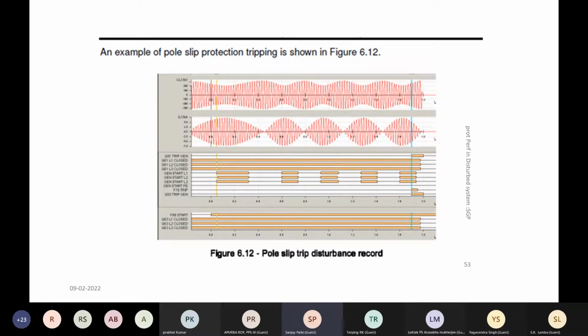Likewise, there is a number of pole slips which a generator can tolerate. Every pole slip results in stress on the generator in terms of mechanical forces. So there is a risk of damaging mechanical components due to torsional stresses, as well as a risk of loosening of the winding within the slot due to vibrations. So pole slip is, I would say, a risky or hazardous condition which should be avoided.